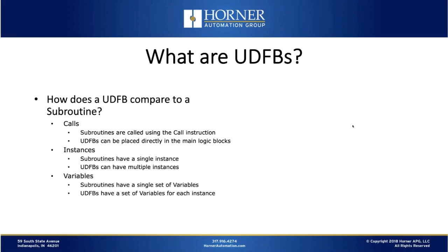One question we get asked a lot is, how does a UDFB compare to a subroutine? Well, subroutines are called using the call instruction. And you can have multiple call instructions throughout your code, but no matter how many times you call the subroutine, you're calling the same section of code with the same variables.